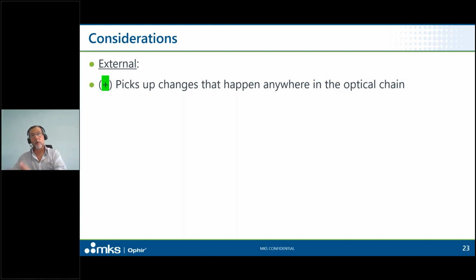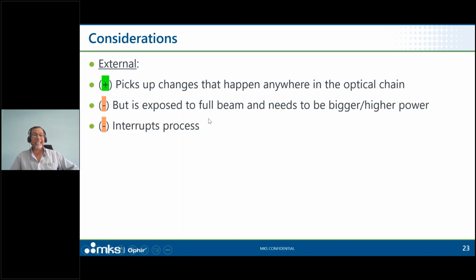So if it's a 100-watt laser, again, I'm going to need a sensor that can measure 100 watts, which means it'll probably be bigger. It might need cooling. It might be more expensive. It might have a slower response time, which may or may not bother me. And I can't have the process happen while I'm doing the measurement. Again, that may or may not bother me, but it's in the equation somewhere.